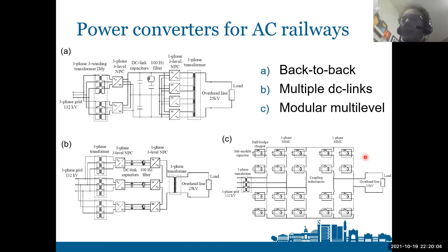The last topology, which also has been explored for 50 Hertz railway, is a modular multi-level topology, which is based on the classical MMC topologies. However, as the input and the output frequency are the same, we cannot obtain a direct conversion of AC power into AC power, but we need to have two separate sections. So we will have a three-phase MMC, which is generating a DC voltage here, with a value of around 50 kV. And then there is a single-phase section, which is then reinverting that DC power back into single-phase AC. This topology is also called transformerless, because by adding a sufficient number of modules on the converter, we can eliminate the need of a transformer on the output side. So this will also help to increase the efficiency compared to the other topologies.